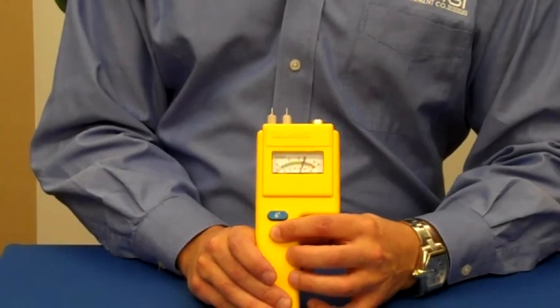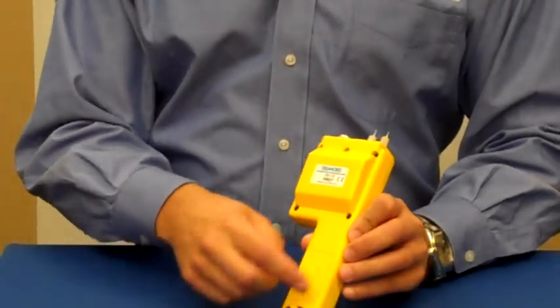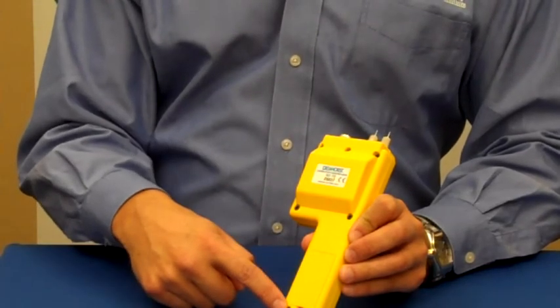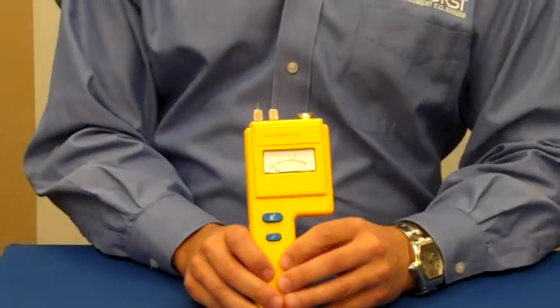If you get a reading of below 20, try changing the battery, which is located in the back of the meter, and then checking the calibration again.